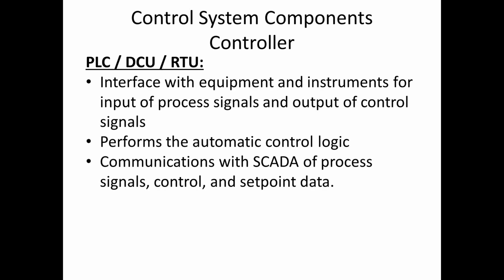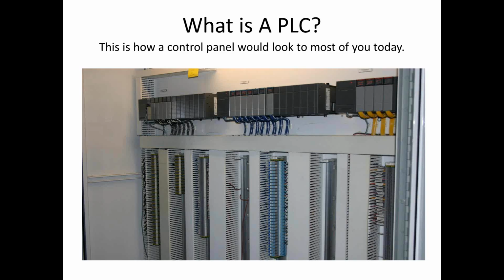But the purpose of any controller is basically to interface with the equipment and the instrumentation for inputs of process signals and output of control signals. So the PLC takes information, performs logic based on that information, and then sends output to the piece of equipment for control. And it also passes along that information to the SCADA system, to the operator, so they can actually see what's going on, they can control it, and if they need to adjust the set points, they can do that as well.